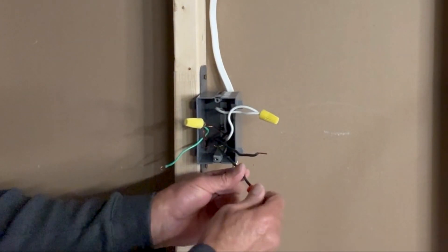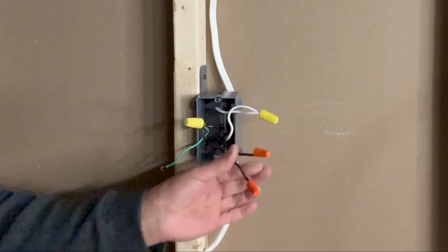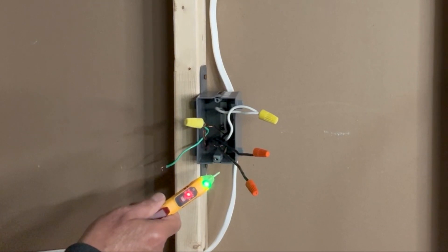So I will temporarily put wire nuts on top of these two black wires and turn on power. With power on I will check which of these two black wires is line wire and which one is the load wire.